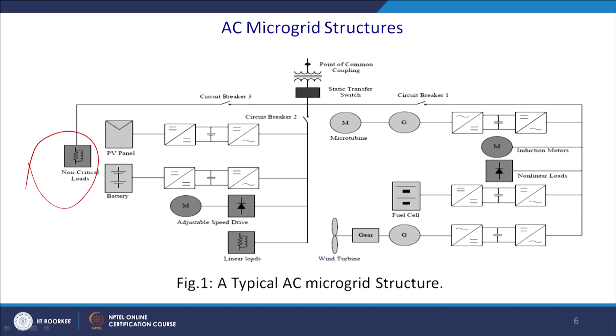You may have an induction motor directly connected to it taking power, and you may have a non-linear load such as an induction machine fed to an adjustable speed drive. You may have a fuel cell, a wind turbine, and also a solar panel, going through DC to DC and then DC to AC conversion, feeding power to the grid. You have a storage element with bidirectional AC to DC conversion. Then you may have adjustable speed type loads, which can be non-linear loads, as well as linear loads and non-critical loads. Based on this, you need to design accordingly. These are the overall typical AC microgrid structures.